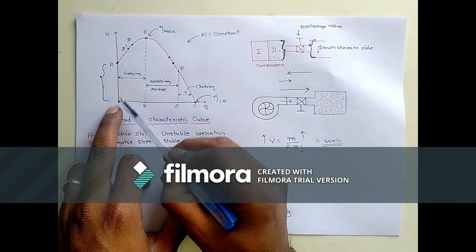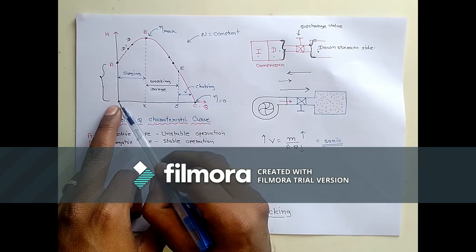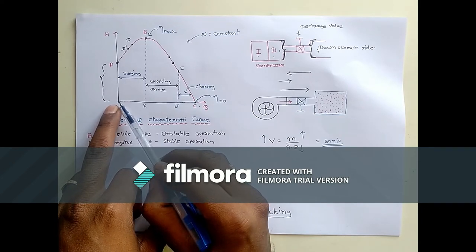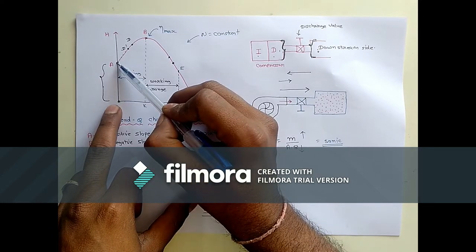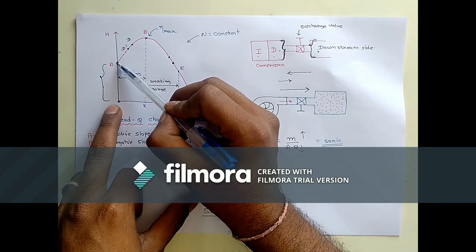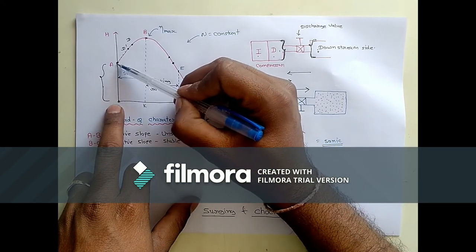In this graph we can see point A. At this point the discharge is 0. What will happen here is the pressure increases from 0 to A. This pressure is due to the impeller. When the impeller is rotating it imparts some pressure to the fluid. So pressure from 0 to A is due to the pressure imparted by the impeller.